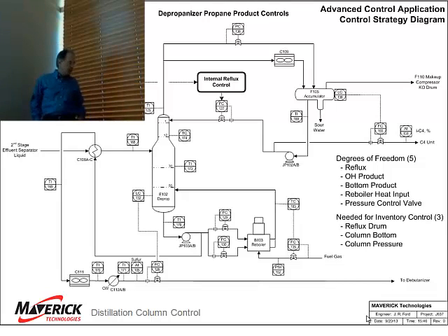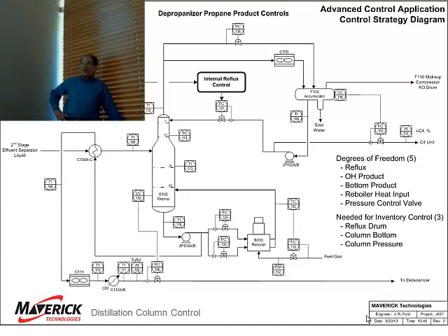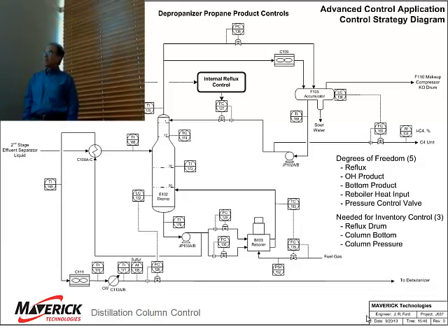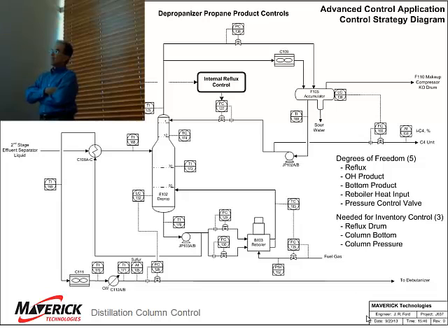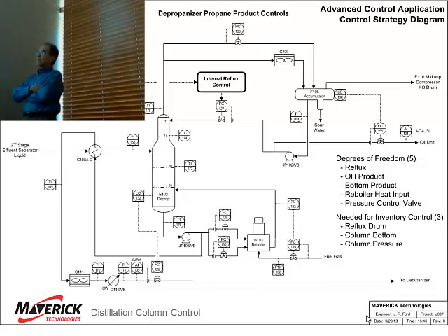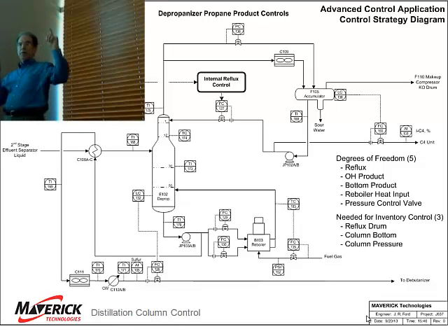On the process identification model: the temperature in the column correlates to purity, and there's a lag before the analyzer reads. When first described it seemed like just a delay — the temperature is this, and 10 minutes later the analyzer reads it. But there's a dead time and a separate lag. The dead time is the time it takes from the sampling point to get to the GC, and the lag is the time it takes going through the chromatograph column.